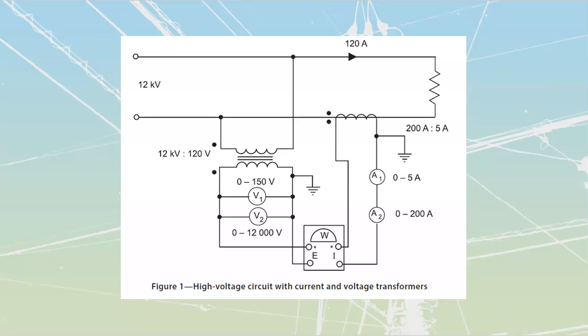meter readings. The first thing that you need to know as an electrician is that it's very rare that you are going to be hooking up the instrument transformers if it is for Hydro. Hydro has got a completely separate branch that is going to go and be the meter technicians. They're the ones who come in and they are going to place all of these components inside of any sort of installation. What we might do is we will just go and prep up for that. We will go as far as having to go and mount our current transformers, the CTs, but we will not go and mount or do the final connections. If we do have voltage, high voltage, we will also have to mount the PTs.